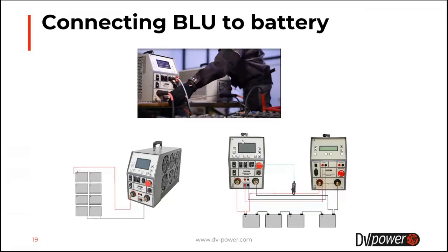If the current of the regular load changes during the test, for example, from 10 amps to 20 amps, the BLU will get the information from the current clamp, and it will change its current to 30 amps in order to keep the total current 50 amps, as we said before. The same applies if you want to use additional load BXL series with the BLU.